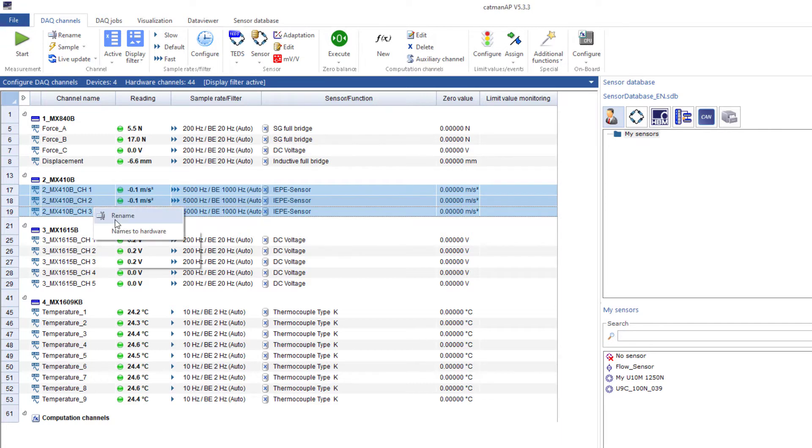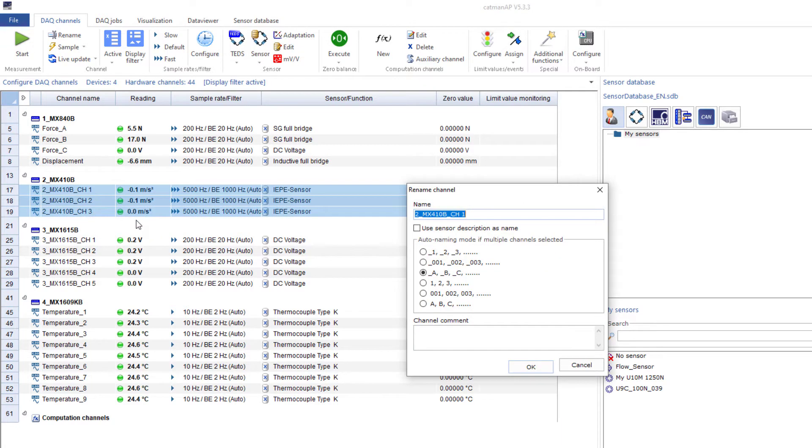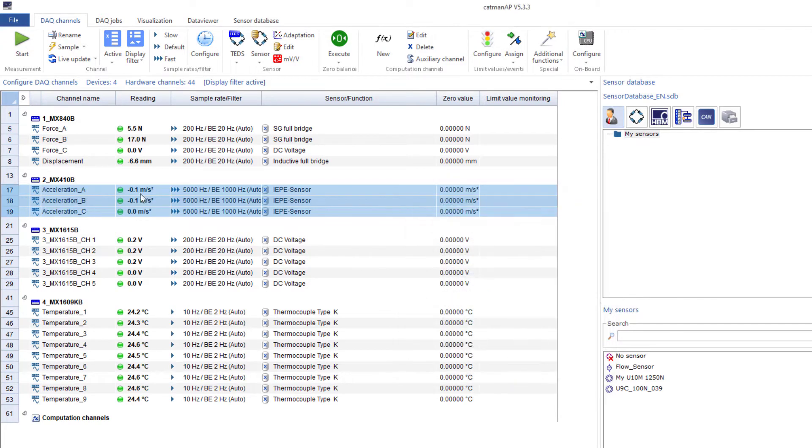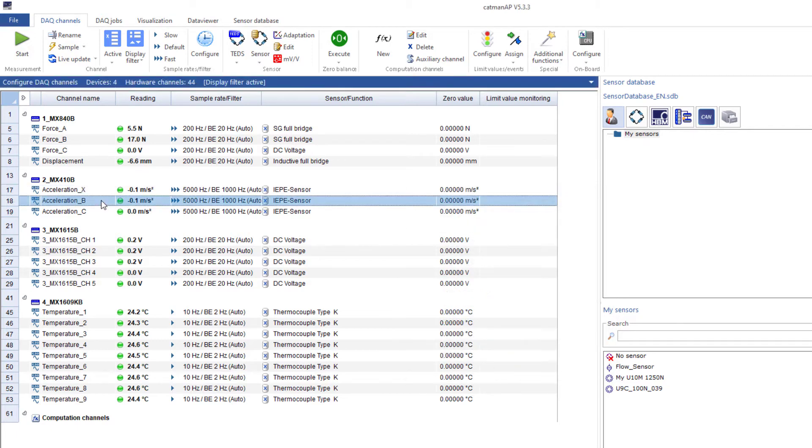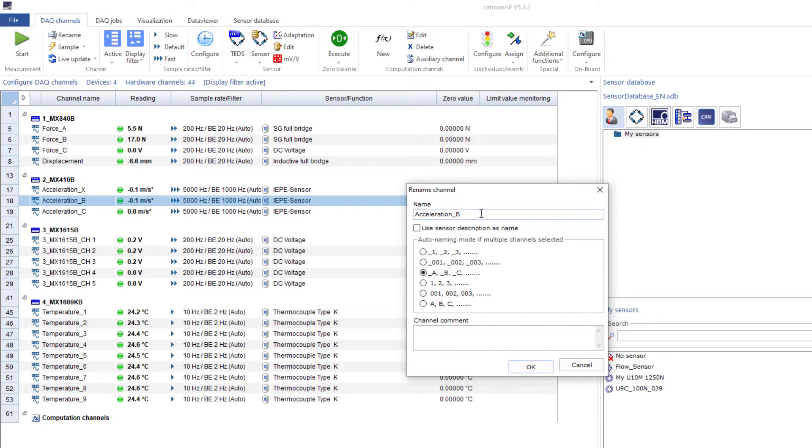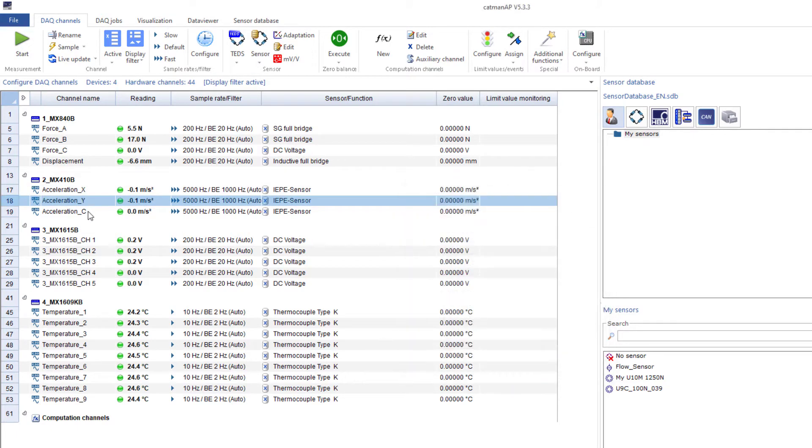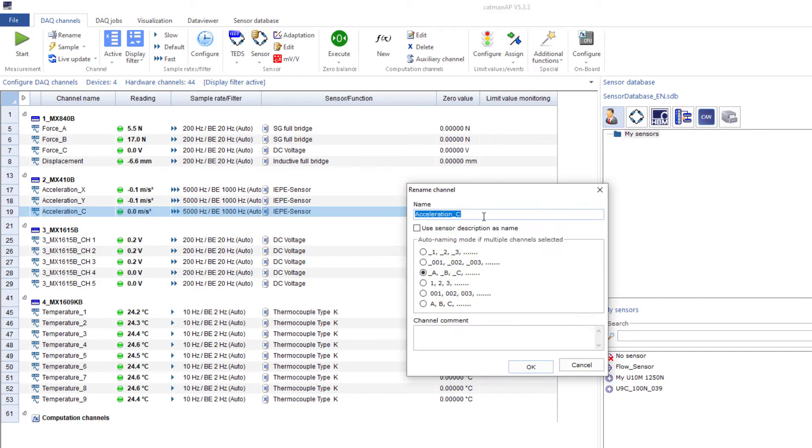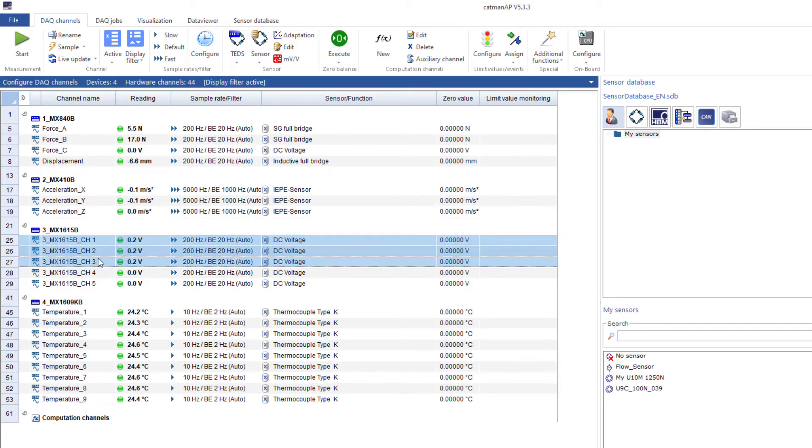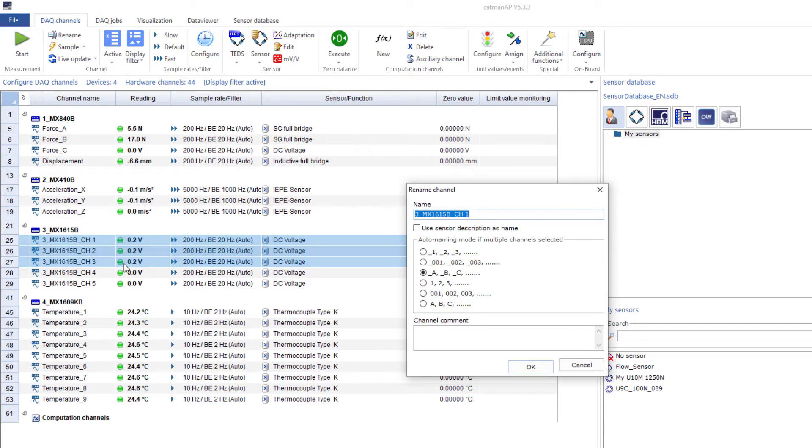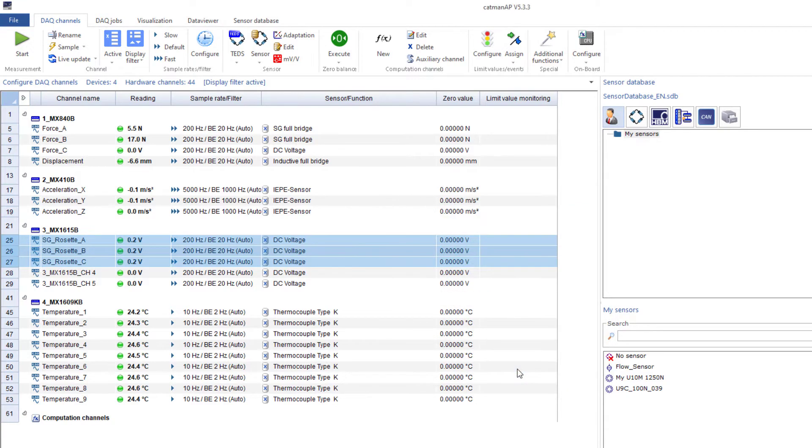The triaxial accelerometer is connected to the MX410B. The sensor settings have already been read out from the TEDs. I'll mark all three channels and then only adjust the direction in the channel name. I'll name the strain gauge rosette exactly the same way and use automatically assigned names also here, so that the three directions are already assigned. Of course, you must pay attention to the fact that the strain gauges were connected exactly in such a way and corrected if necessary.